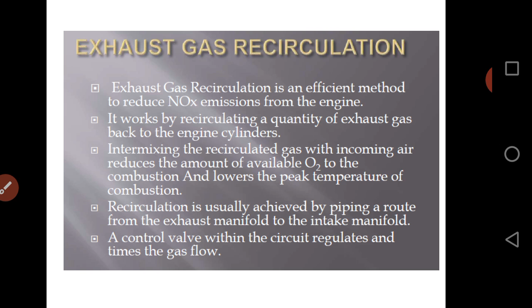So obviously there will be a reduction in oxygen. What will happen if the oxygen available for combustion is reduced? We can control the formation of NOx. So here the concept is that we are reducing the excess oxygen level for combustion, by mixing exhaust gases with the incoming air. As the oxygen available for combustion is reduced, it controls NOx formation. For that we use a control valve to regulate the quantity of exhaust gas to be recirculated.